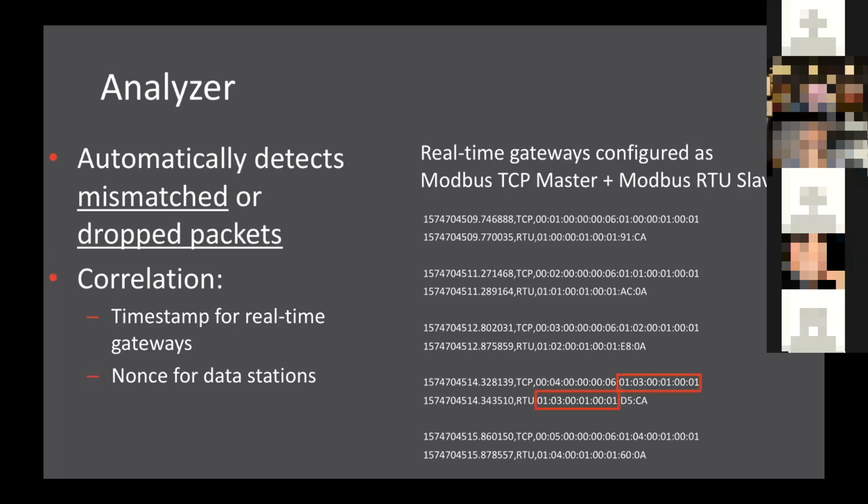If you look here on the right-hand side, you can compare the key data, the actual payload that was being sent, as well as all the extra data prepended to the Modbus. It has the transaction ID, the protocol ID, and the size for the Modbus TCP side. And then you can see the RTU CRC at the end on the Modbus RTU side.